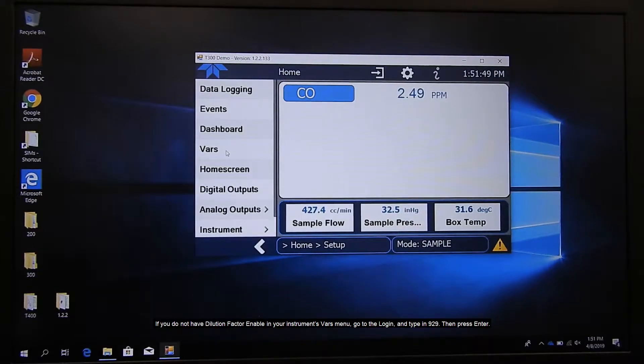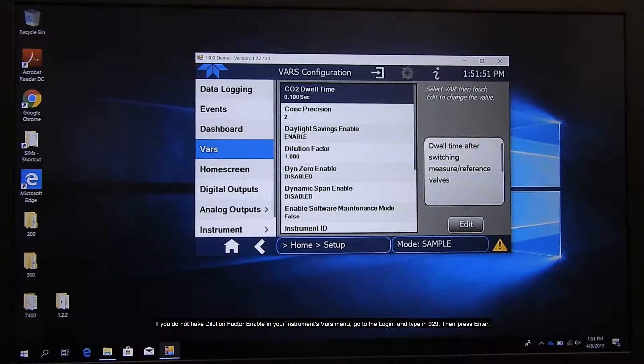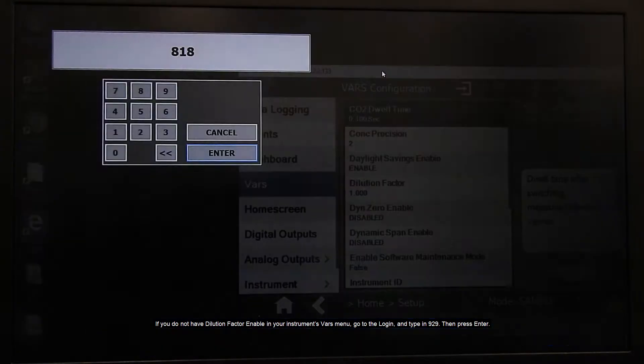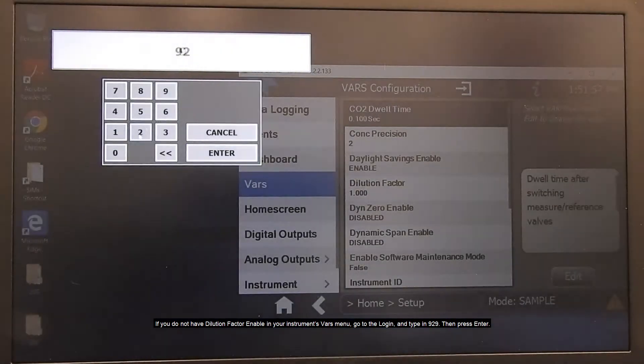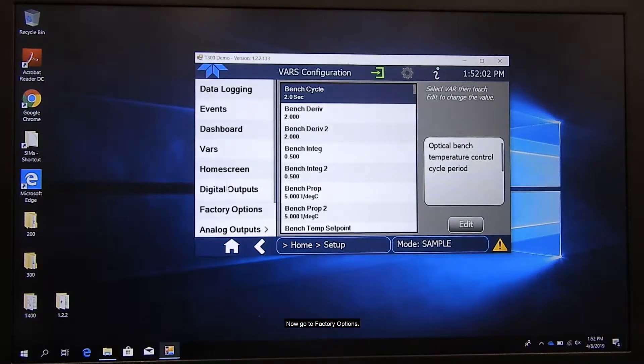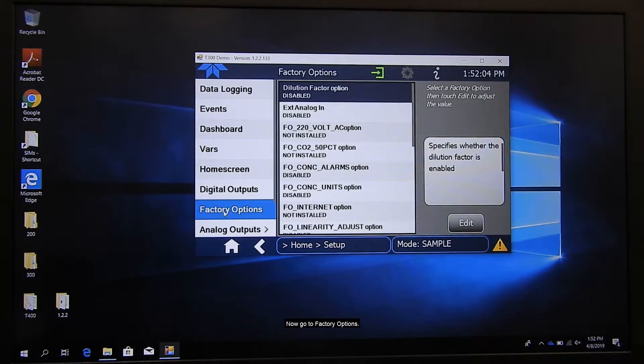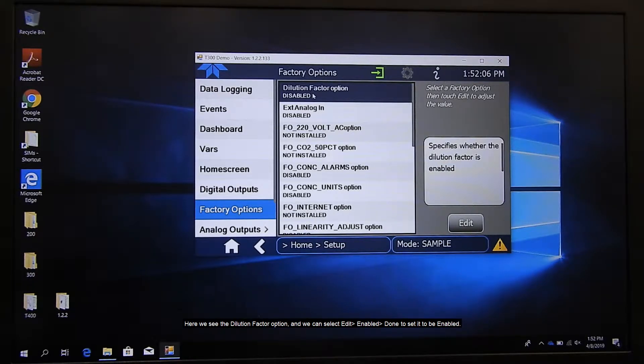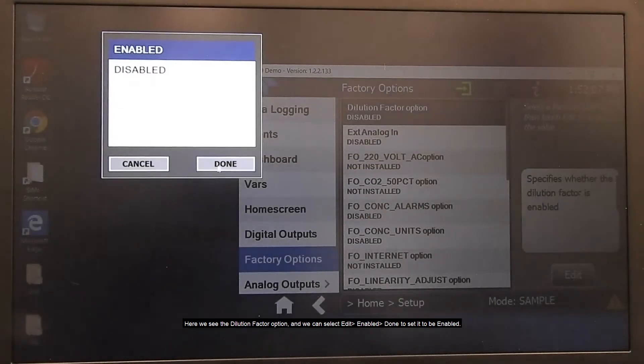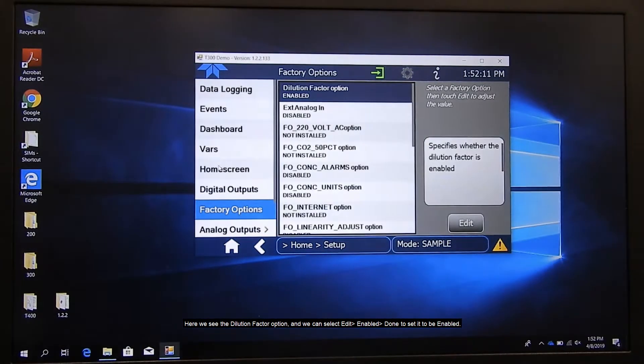If you do not have Dilution Factor enabled in your instrument's VARS menu, go to the Login option and type in 929, then Enter. Now go to Factory Options. Here we see the Dilution Factor option and we can select Edit, Enabled, Done to set it to be enabled.